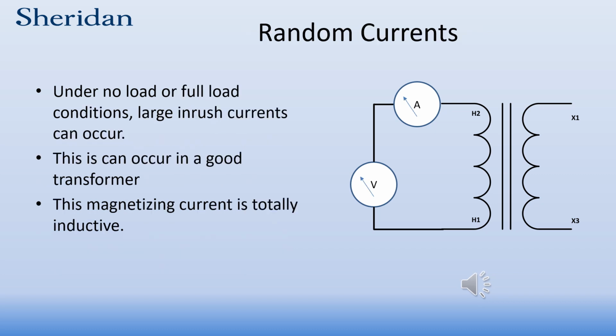Also, in practical transformers, under no load or full load conditions, large inrush currents can occur. They actually can be large enough to trip or blow the overcurrent protection. This can still be a good transformer. This doesn't mean that the transformer is bad. This magnetizing current is really totally inductive. It is just that current that occurs to try to build up and charge up that magnetic field once the transformer is energized or put online.